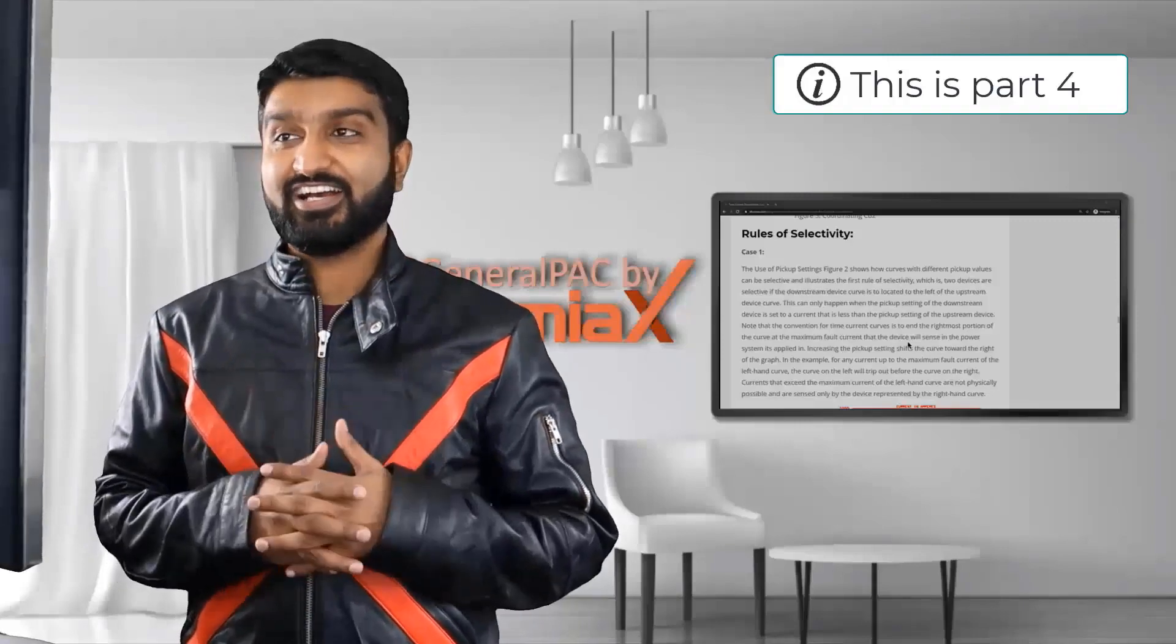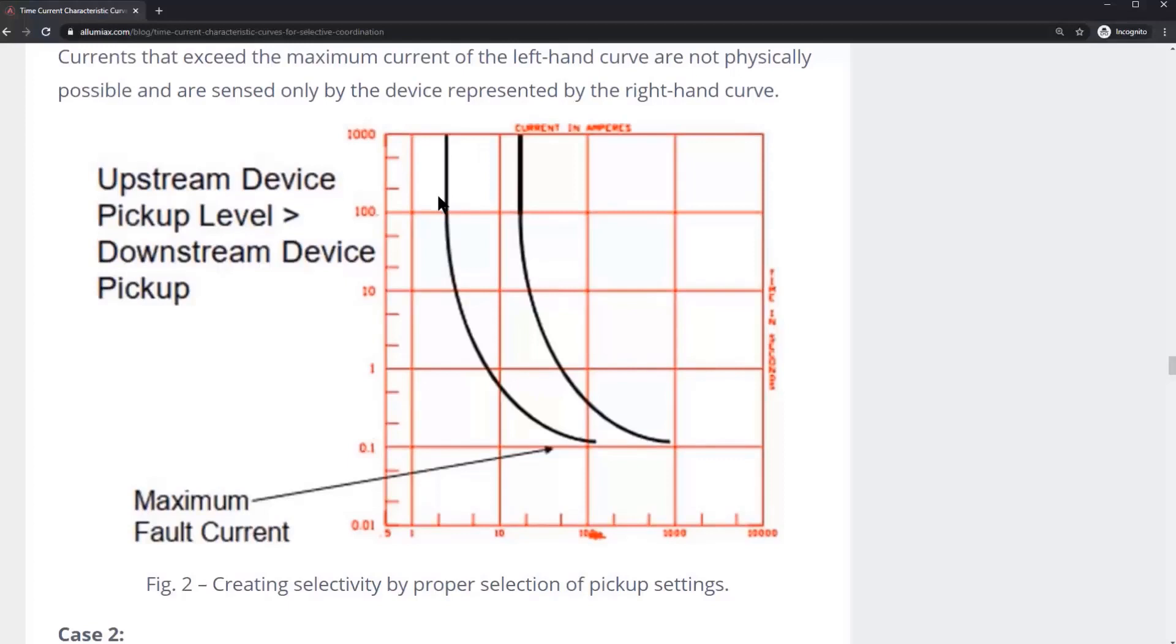In this part we're going to go over the rules of selectivity. This right here would be considered as the pickup setting. This is for breaker number one or relay number one. And this point right here is the pickup setting for relay number two.